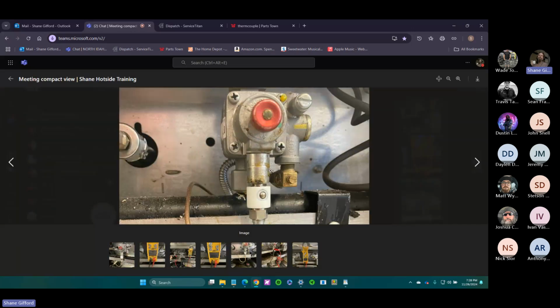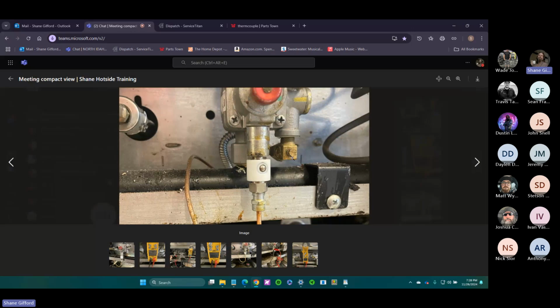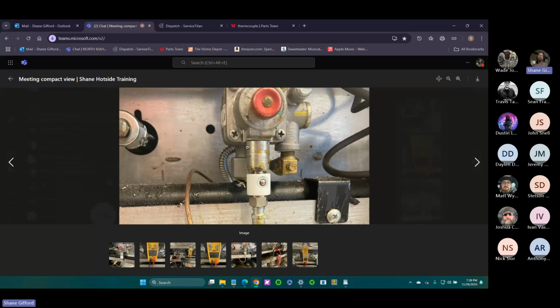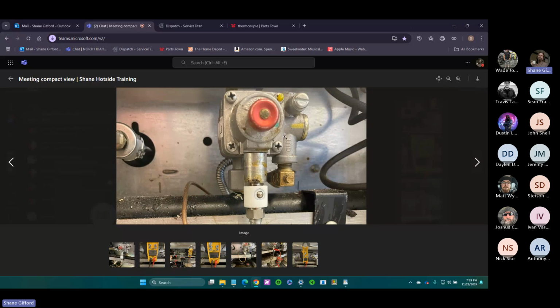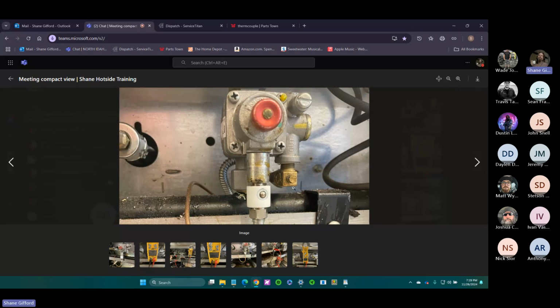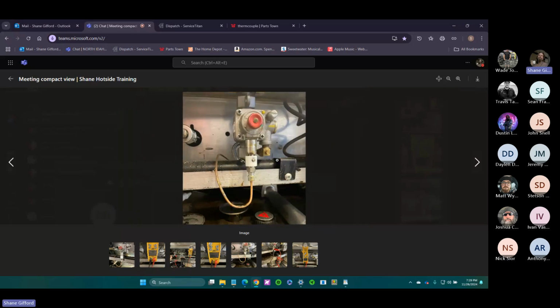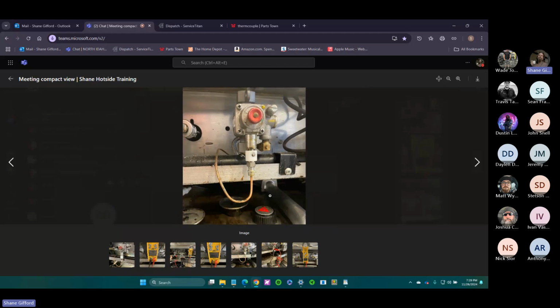So you just got to look at the metal, look at what you're working with. And on this one in particular, you can adjust your pilot flame. You back the screw in and out, and that will adjust the actual pilot flame. If you've got a weak flame, look at what the manufacturer says the pilot flame ought to be, and if you're not running that, use this screw to change your flame. You can really dial these things in, and all the information you need you can find within 30 seconds to a minute of searching for it.